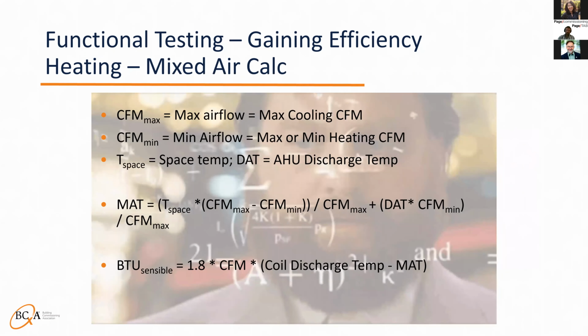So with this slide, we're going to go over a little bit of the sensible heat equations and how to calculate mixed air temperature. And if you want to figure out the temperature entering the reheat coil on a series box, you can use this equation. And honestly, both these equations should be memorized. To figure out return air temp for this calculation, I usually use space temperature for mild days or 5 degrees higher than space temperature for hotter days. You can also just measure it and assume it's roughly the same with all associated terminal units.